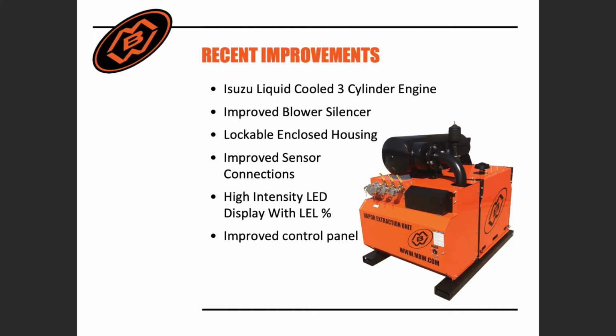The LED lights have been added to the control board and the sensor. It is much easier to see where you are at in LEL levels when running the machine now. The control panel has come a long way. We added a user-friendly control board that tells the operator everything they need to know while running a VEU. It has the air bypass valve, LED lights, glow plugs, engine start and stop, and alarm test buttons. We have gone keyless with this machine.